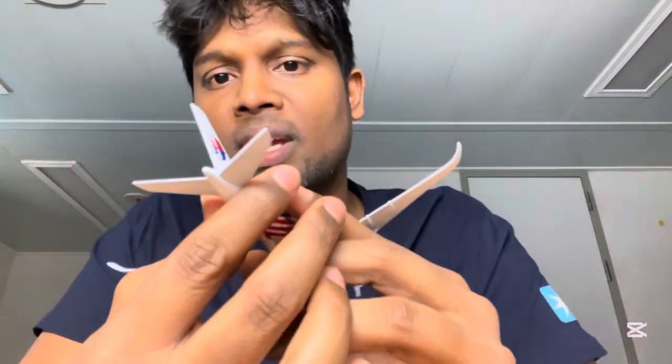So you have to make sure first the electrodes are giving spark. To ensure that electrodes are going to give spark, the transformer should be in good condition, as well as the electrodes should be at equal distance. For example, I just have this toy with me. So we can consider these are the two electrodes through which spark is coming, and this one through which the fuel will be coming.